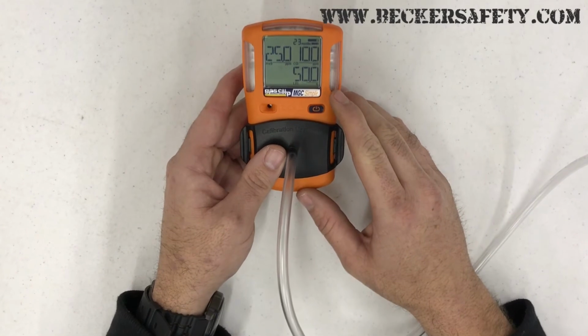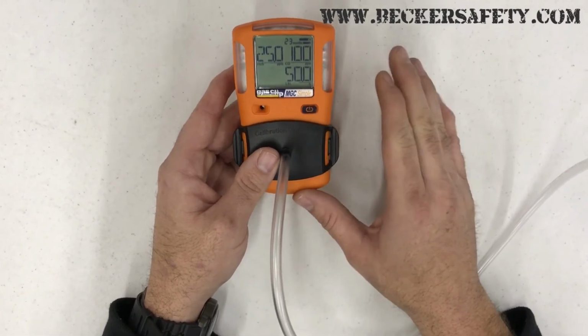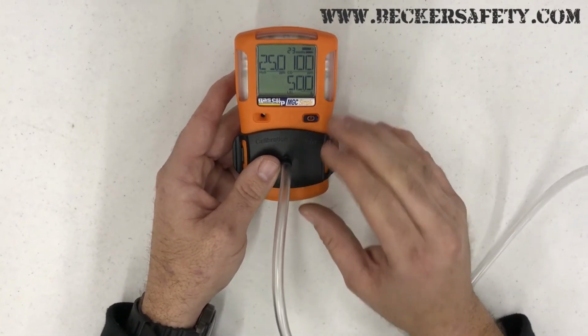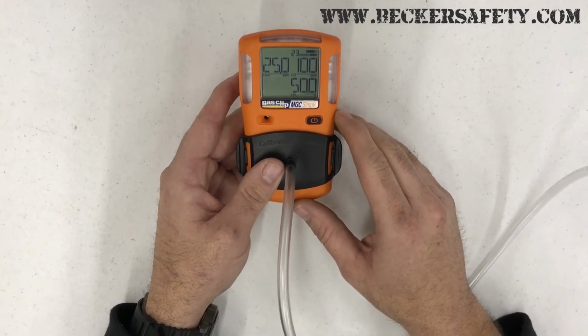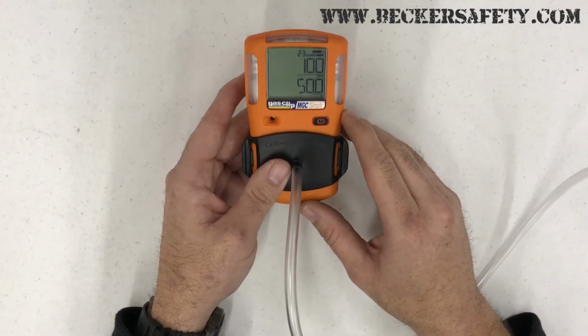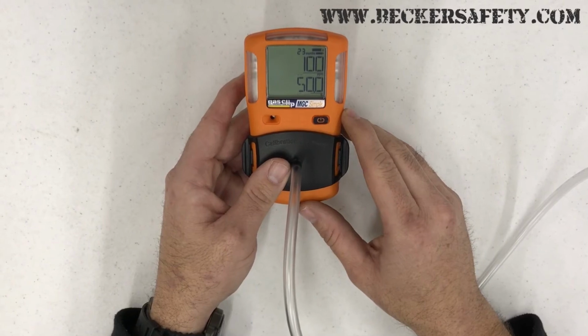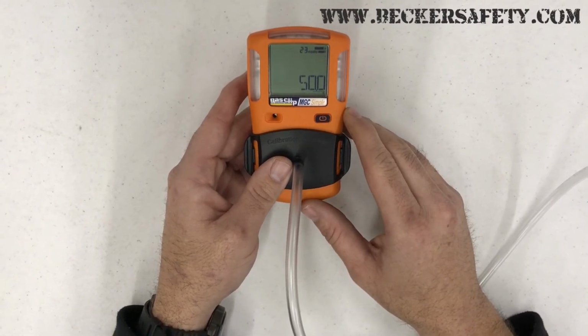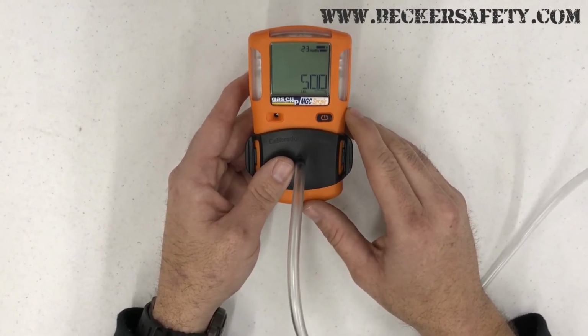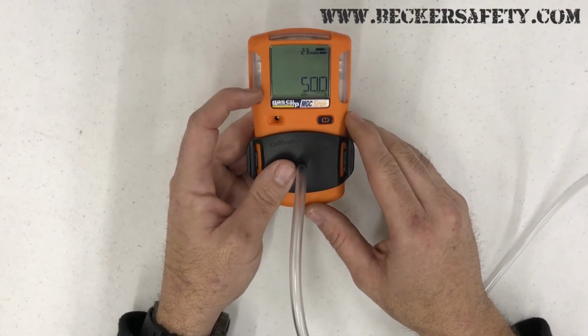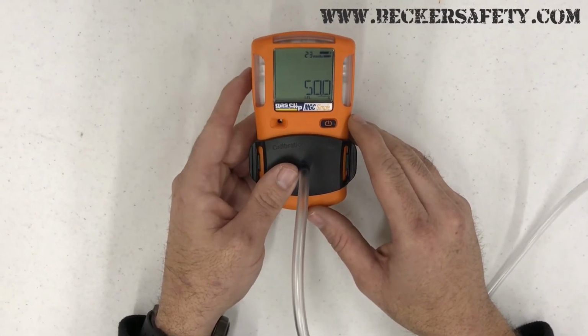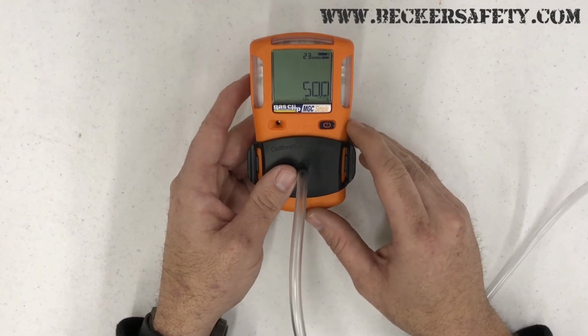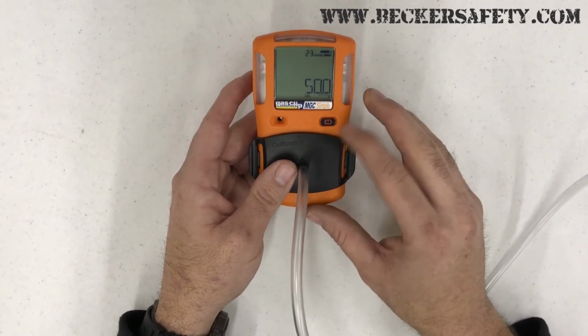So you see it got to the 50. Now it'll have to stay stabilized for a minute, and then it'll beep and you will be complete. If you notice, as they steady out, they will disappear once they're good. LEL is always going to be your last one to go out because of the size of the sensor.